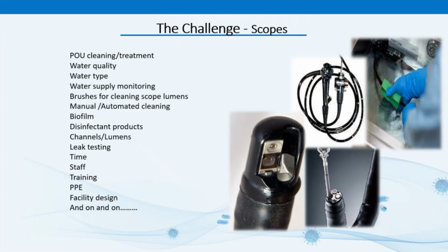No wonder improper endoscope reprocessing has been identified as one of healthcare's most dangerous technology threats. Reprocessing endoscopes involves multiple steps, including pre-cleaning, cleaning, leak testing, disinfection, rinsing, drying, and proper storage that are specific to the brand of the device, so there's lots of variabilities in IFUs and products.